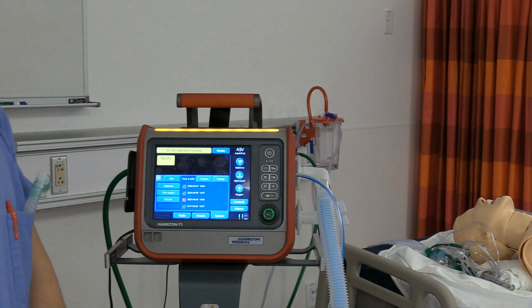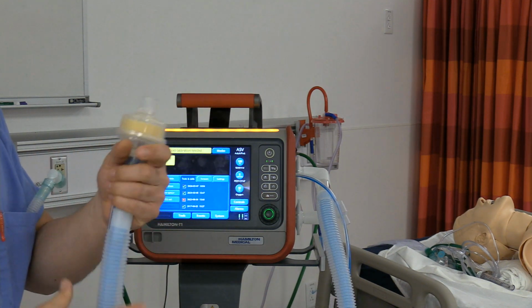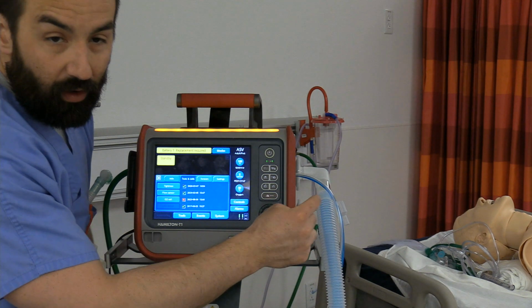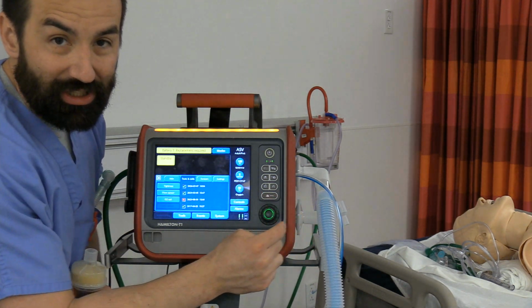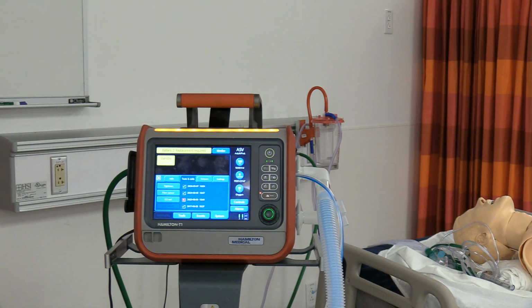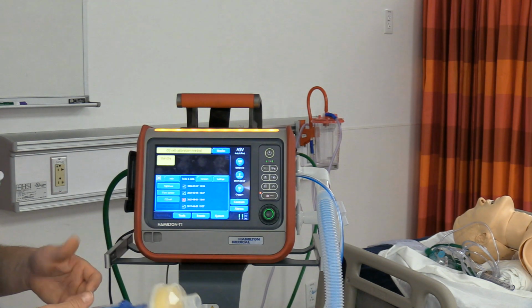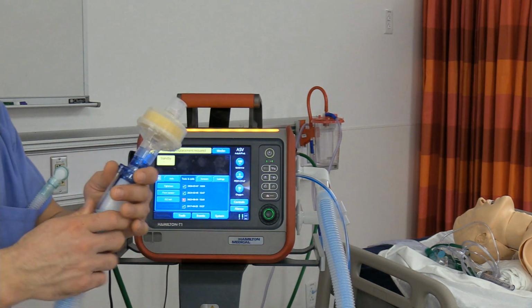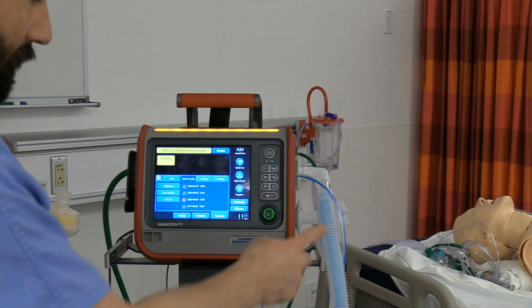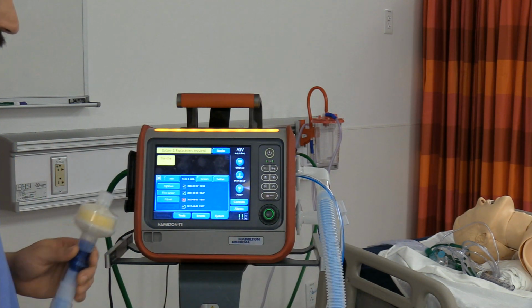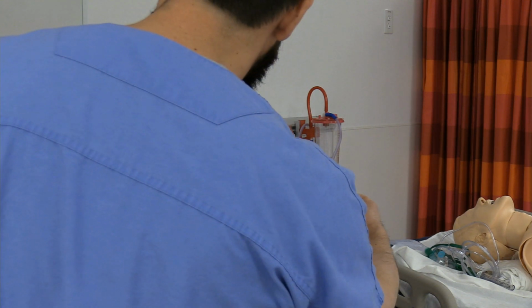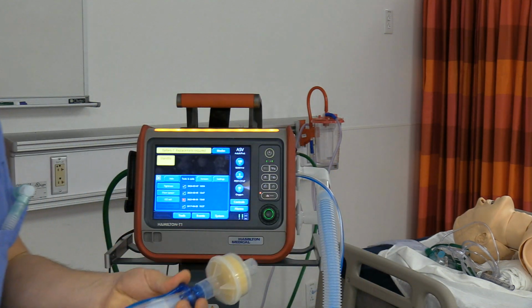If you cannot get this to pass, start with basics, checking your connections and stuff like that. But if all else fails, go back to that exhalation diaphragm. That's usually your culprit there. It's not seated right, or it's not locked in, something like that. Sometimes it can be some other weird, obscure thing with your circuitry, but typically I find somebody messed up on that exhalation valve. The flow sensor here, same, just like all the other Hamilton ones.